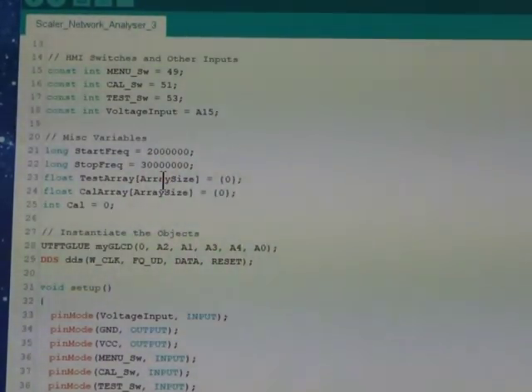I upped that to 500 because I was noticing that when we first go into the test and calibration, there must be some shock or a little bit of settling required to get good accurate figures. So I thought I'd go to 500, ditch the first 20, and only start plotting and recording from position 20 onwards, and that's certainly cleaned up the data significantly.